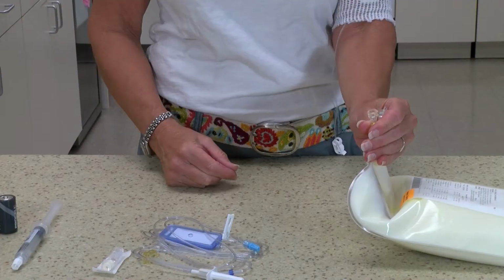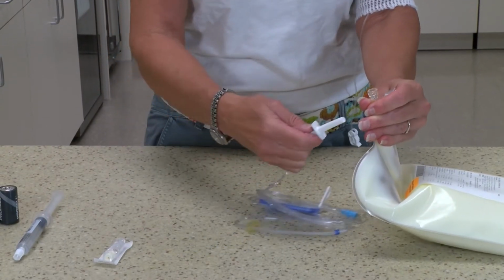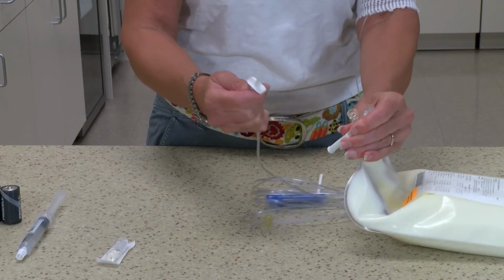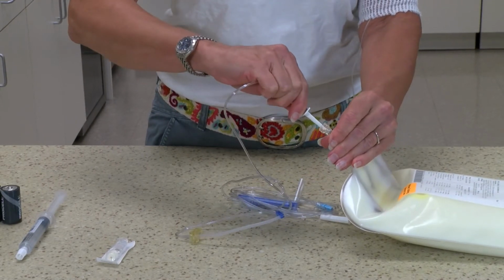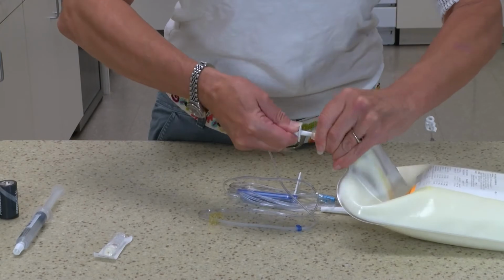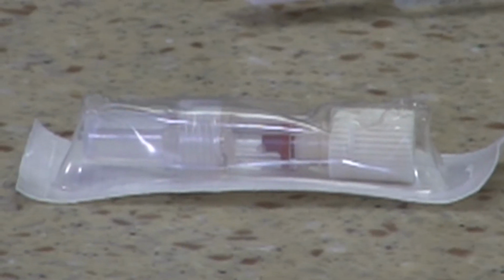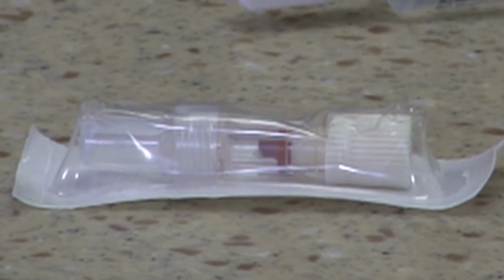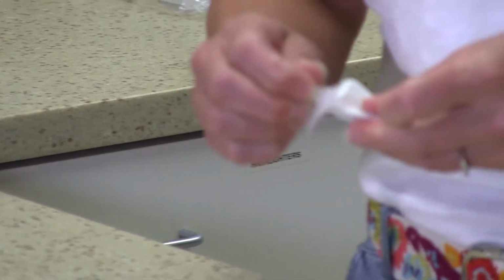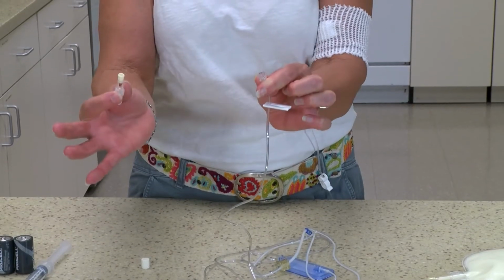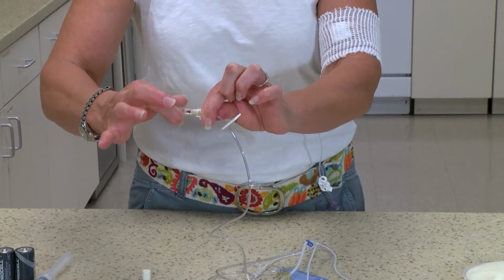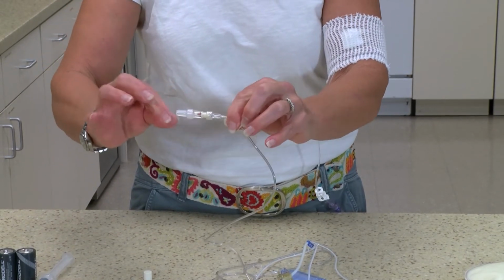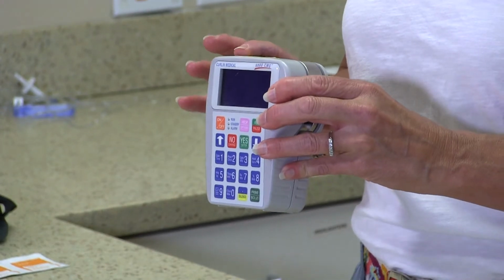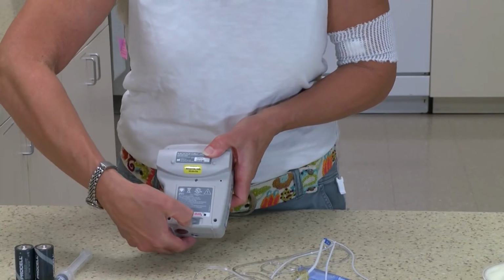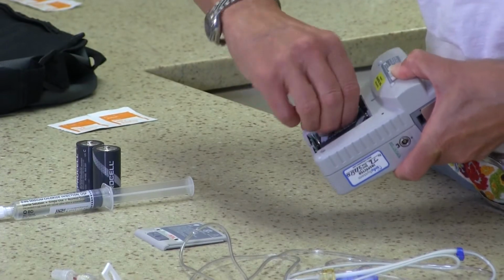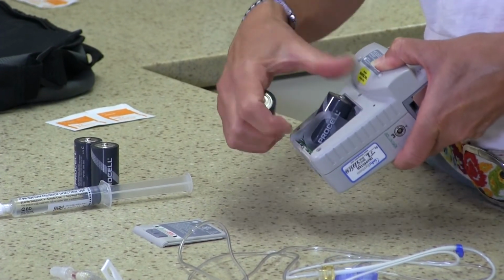Now, remove the plastic cover on the spike of the tubing, and with a pushing and twisting motion, insert it into the PN port. Now, open the additional filter and place it on the end of the tubing. Now get your pump. It's a good practice to change the batteries every day, so this is a good time to replace the batteries.